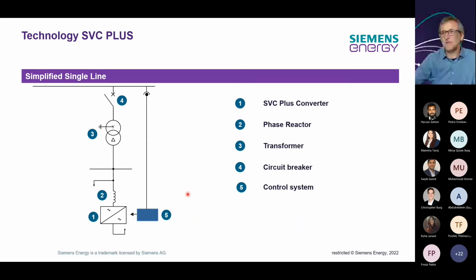The STATCOM, very simplified in a single line diagram. We connect it to the high voltage grid, whatever voltage it is, through a circuit breaker. Normally we would use a step-up transformer. If the voltage is lower, at medium voltage, we might connect it without. But in our cases, on the high voltage grid, we would normally use a step-up transformer. Then we have a medium voltage bus where we have the STATCOM itself, with the converter. We have a phase reactor in between. And of course, there's a control system to manage all that. In most cases, it will collect the values from the HV grid and control against that.